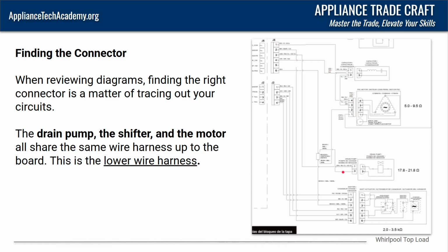Now the next one, this will probably be our neutral. Comes up here, over here, comes into a splice, and you can see this splice also provides neutral to the shifter and over here to the motor. Nonetheless, we're not really worried about those. We're only worried about, right now, the drain pump. So tracing that out, comes up here, splices in there, and then it comes up right there. So the same connector we were just looking at, blue and white.